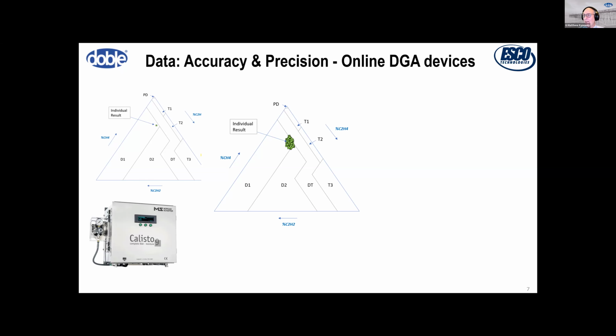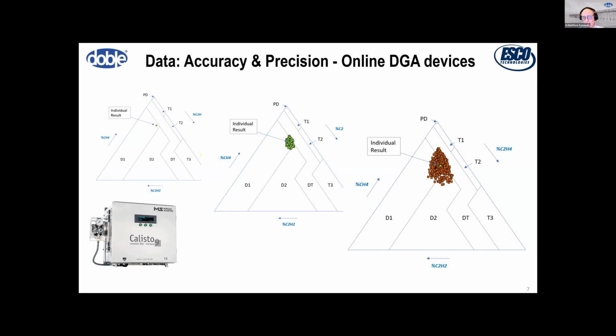Now let's go up to the highest levels of accuracy based on the type of DGA online monitor you might select. Now we look at them and go, wow, there might be more sitting in DT or D1—maybe it's a tie. You start to see that it fundamentally changes the actual output, the actual failure mode, which would in turn probably change the way you respond to this kind of alert coming off your SCADA system or condition monitoring system directly to the utility asset owner.